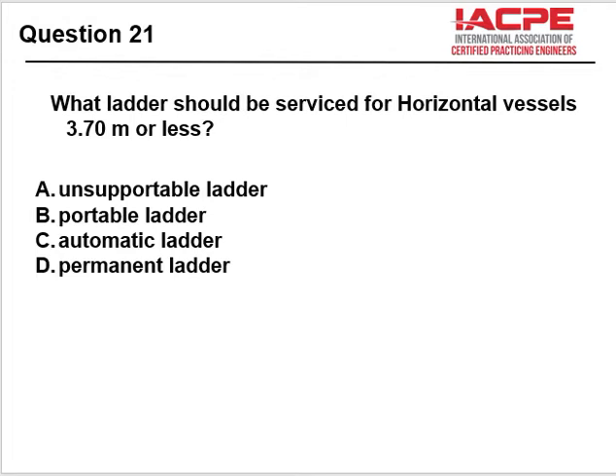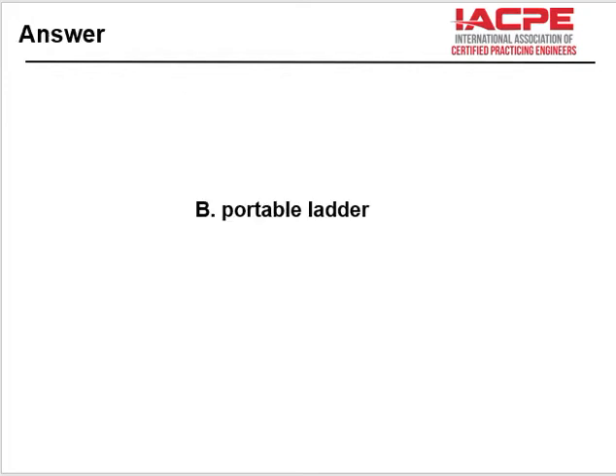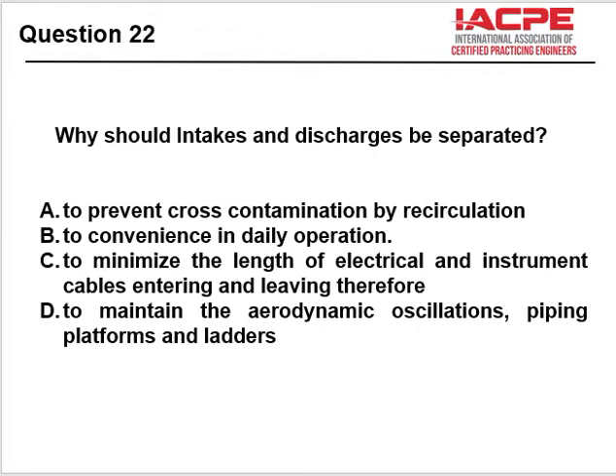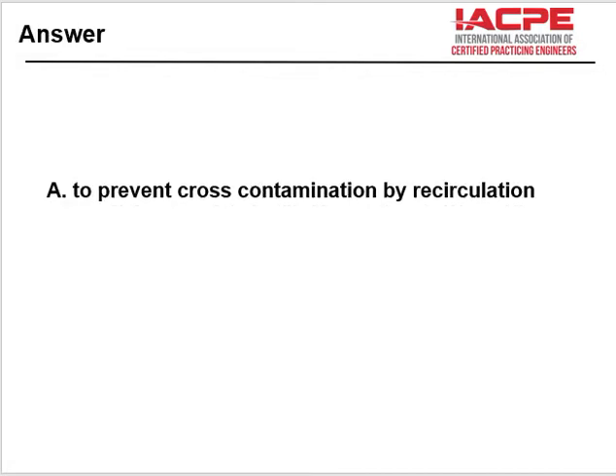What ladder should be used for horizontal vessels? 3.7 meters or less. Unsupported, portable, automatic, or permanent. So if it's very short, you can use a portable ladder. Why should intakes and discharge of equipment be separated? To prevent cross-contamination, convenience in daily operation, to minimize the length of electrical cables, piping, platforms, and ladders, to prevent cross-contamination from the suction to the discharge.